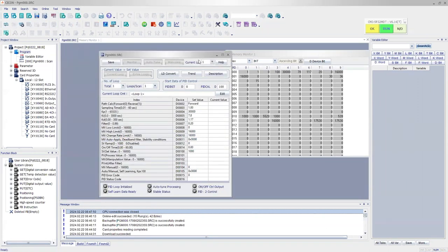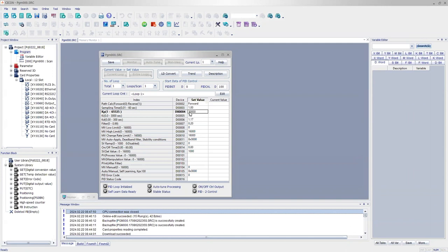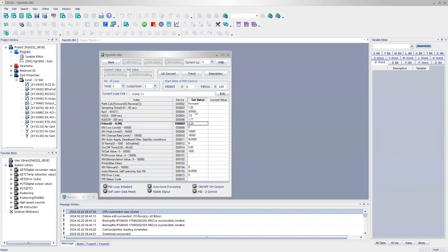Going back to the PID program and disconnecting — what do we notice right away? These three values changed. The KP, KI, and KD all changed on their own. I did not change these. Auto-tuning changed KP from 8,000 to 30,000, KI to 7.8, and KD — which we had set to 0.01 — is now 1.17. The filter got changed as well. These constant values were changed based on the auto-tuning process. We take care of the heavy lifting for you.